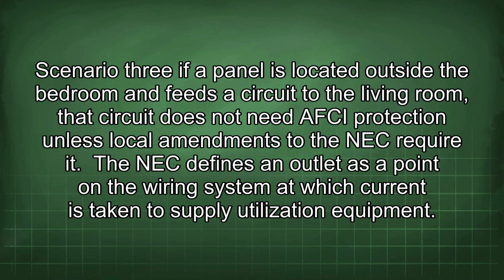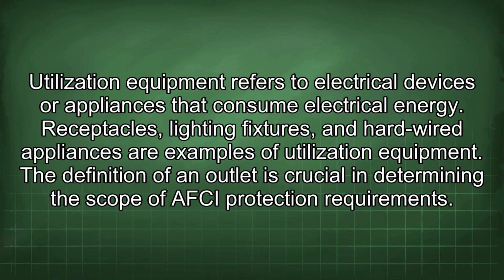The NEC defines an outlet as a point in the wiring system at which current is taken to supply utilization equipment. Utilization equipment refers to electrical devices or appliances that consume electrical energy. Receptacles, lighting fixtures, and hardwired appliances are examples of utilization equipment. The definition of an outlet is crucial in determining the scope of AFCI protection requirements.